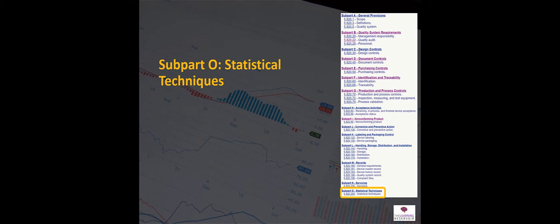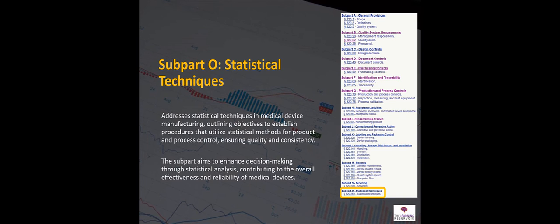And if you use statistics in your processes — which is highly likely because we're dealing with manufacturing situations — what are the statistical techniques you're using and why have you chosen those particular methods? The requirements for that are outlined in sub-part O. And that is a whirlwind tour of 21 CFR 820. I hope it gives you an understanding of the structure and the content of this particular regulation.